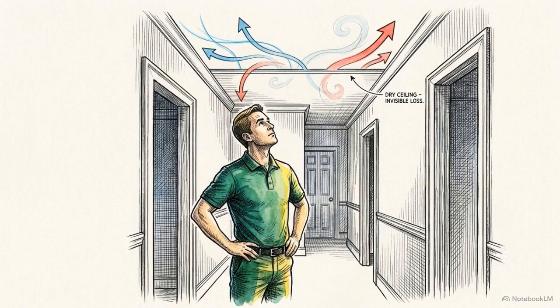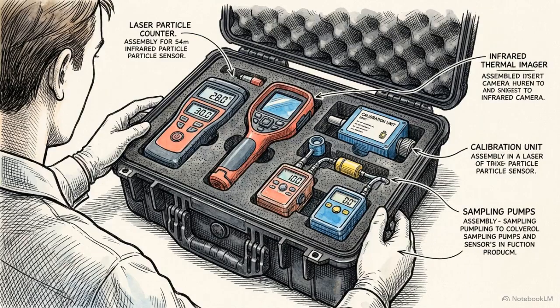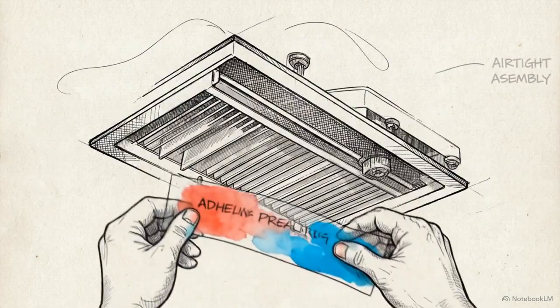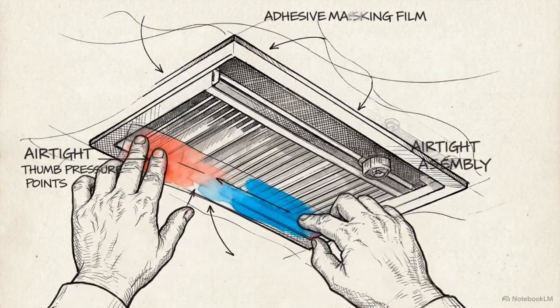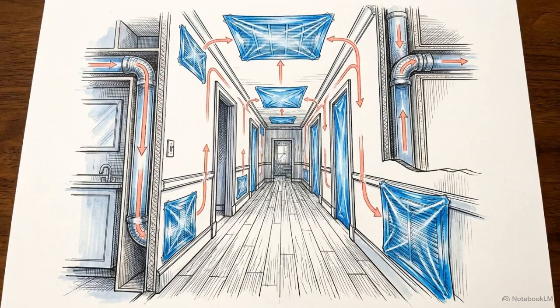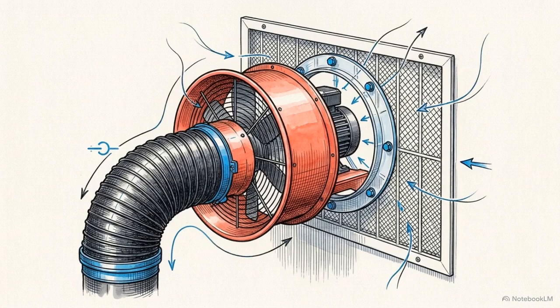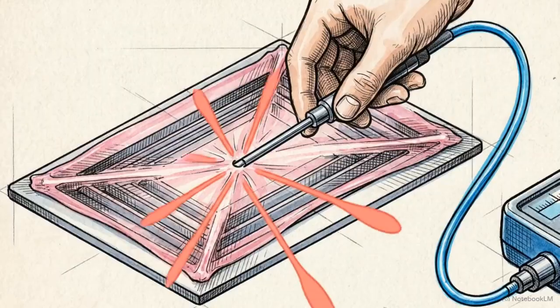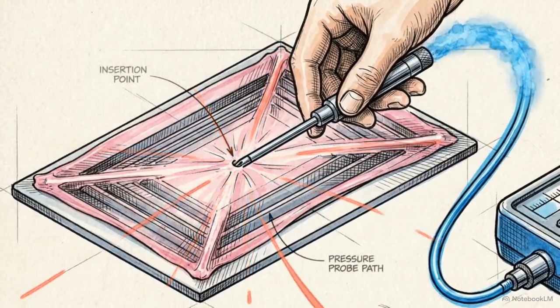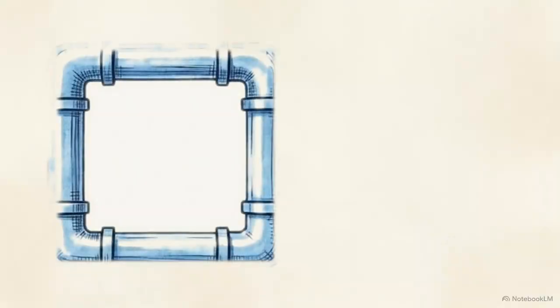Escaping air is invisible, which leaves investigators with a dilemma. To prove a hidden leak exists and measure its severity, mold assessors must rely on specialized diagnostic tools. The primary instruments for this job are a calibrated testing fan and a digital manometer gauge. The testing protocol starts with isolation. An investigator places airtight adhesive masks over every single supply and return grill inside the home. This separates the duct system from the ambient air in the rooms. Next, they attach the calibrated fan directly to the main return grill using a flexible tube. A small static pressure probe is inserted through the mask of a nearby supply vent, connecting the hidden ductwork to the digital manometer. This diagram illustrates the pressurization phase.